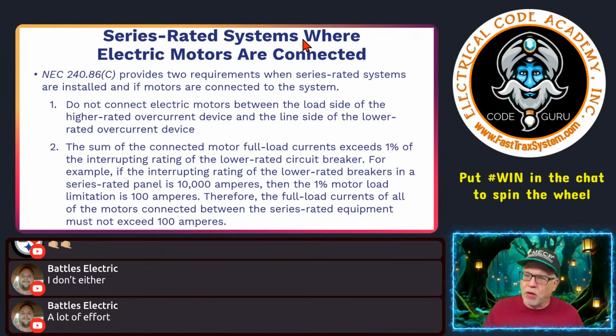Series rated systems where electric motors are connected. So in 240.86(C), notice we're in .86(C), okay, that is just for motor contribution. That means what is the motor going to be giving to the circuit? Y'all heard me talk about the fault current and the contribution. Yes, it comes from the utility, but motors can also give a certain value back, because motors really are just generators. So here's what it says.